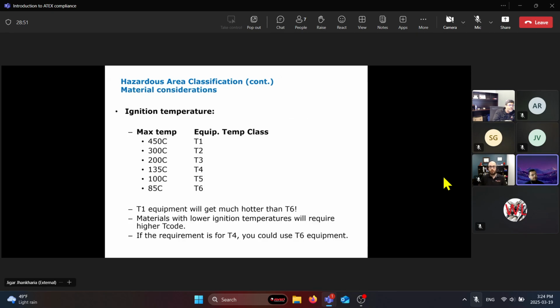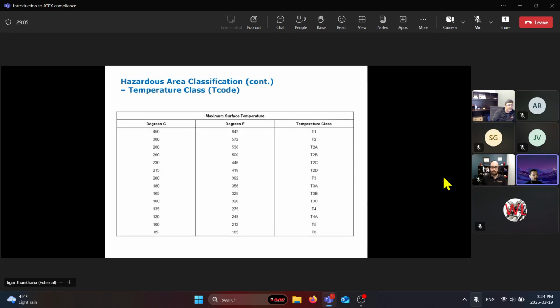And usually T4 is the most common temperature classification we come across on products. There's only certain products that can reach a maximum temperature of 450 degrees, so you don't see those that often. And basically this list or this table shows the differences, degrees in Fahrenheit, and the temperature class it reflects. And these are available pretty much on any certification body's website, like a poster where it lists the different methods of protection as well. So you can always refer there.